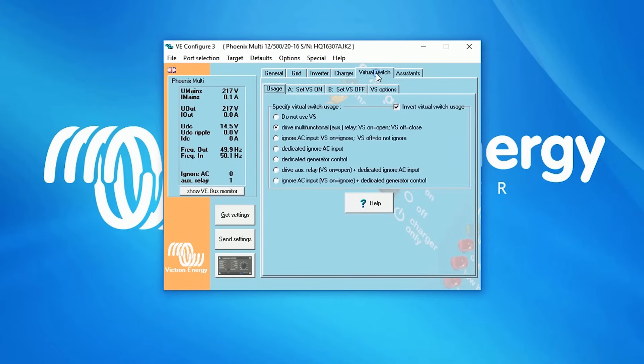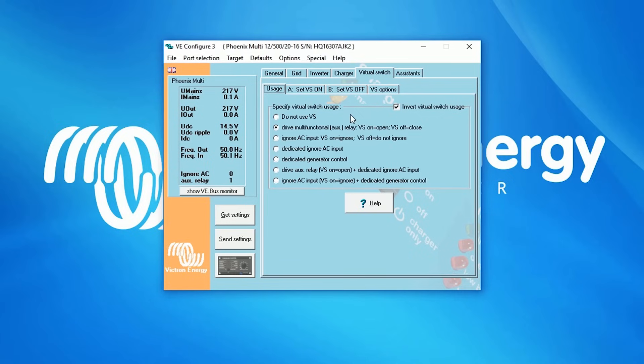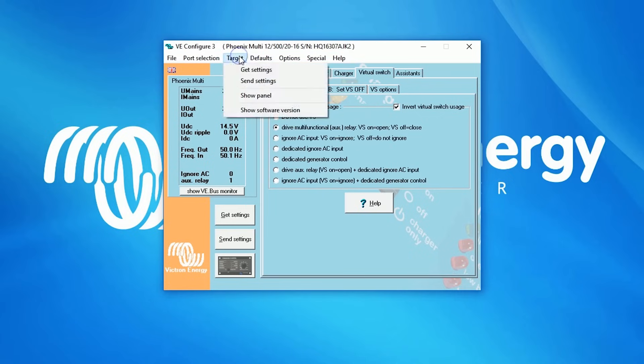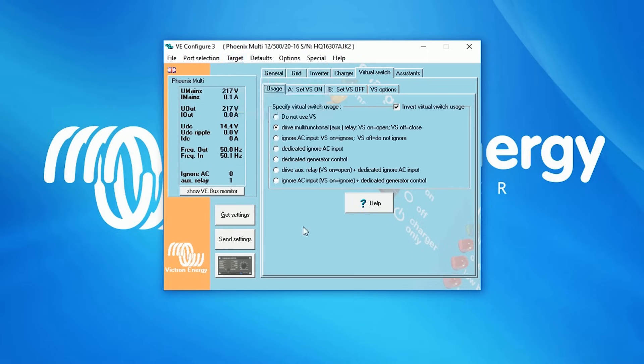At the Virtual Switch tab, you can program alarms, pre-alarms, relays, ignore AC input, and generator start-stop. If you have made all necessary changes in the settings and you would like to apply them to the device, select Target in the menu above and Send Settings, or click the Send Settings button in the lower left corner of the VE Configure screen. The configuration will be sent to the device.